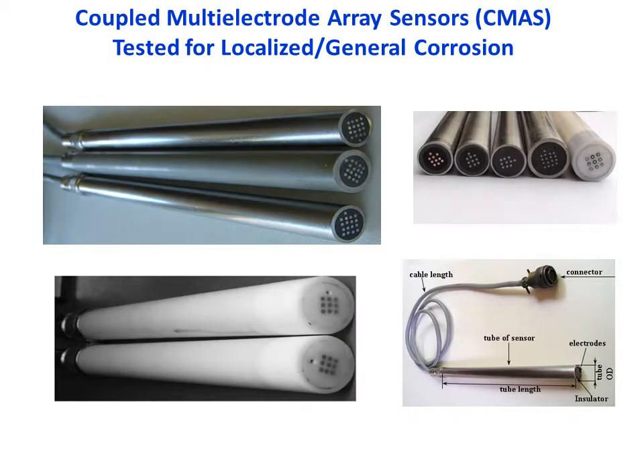CMAS probes are pictured in this image and can be manufactured with 9, 16, or 25 electrodes. The electrodes are machined from the type of metal being utilized in the client's process, and for special cases, the client can send Corr Instruments a sample of their metal to be machined into electrodes such that the composition of the electrodes match the composition of their metal. The CMAS probes can be manufactured to a variety of insertion depths, and due to the length of the probe itself, the life of the probe can be up to 20 years or more, depending on the corrosion rate the probe is exposed to.